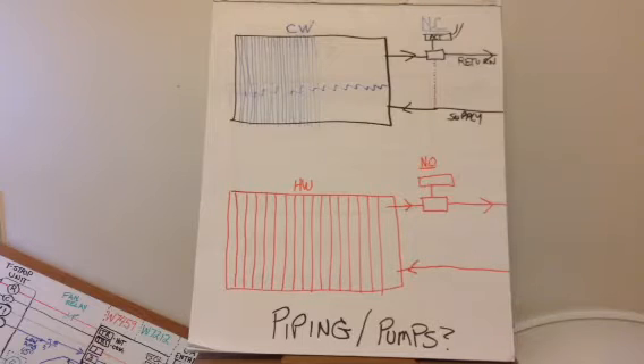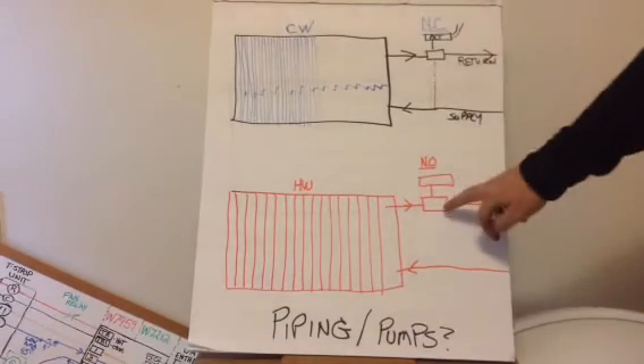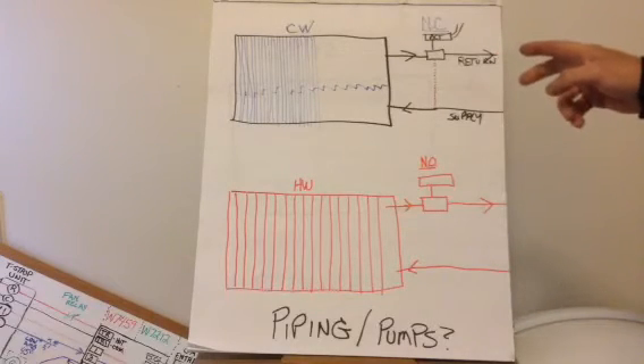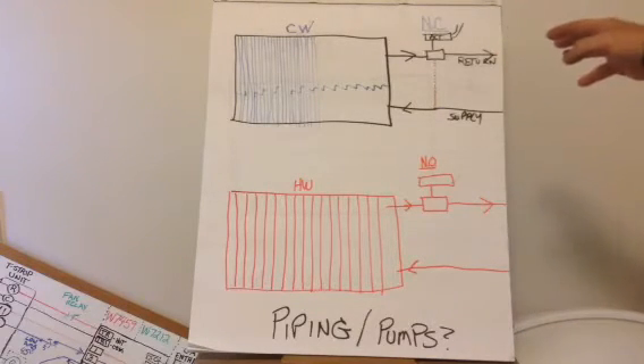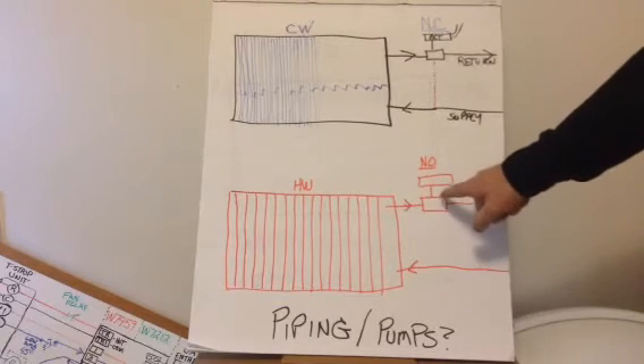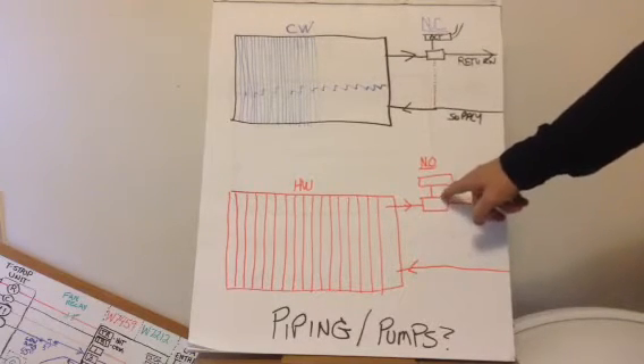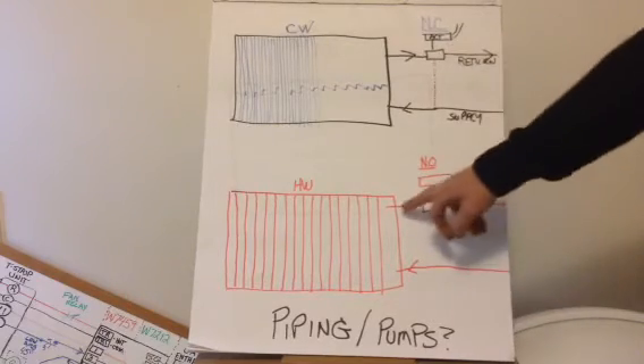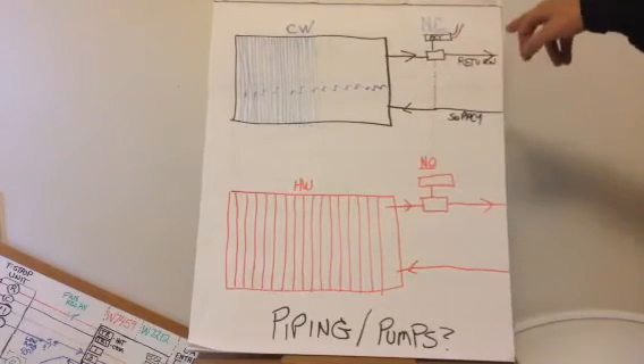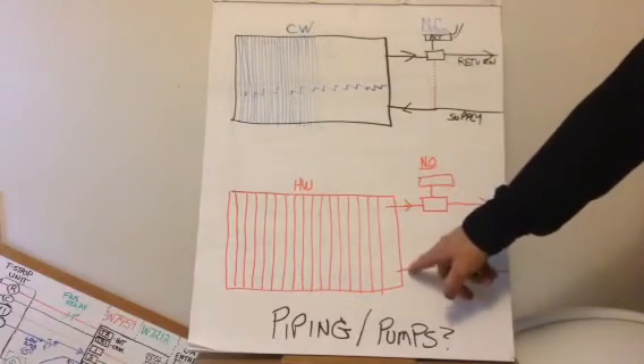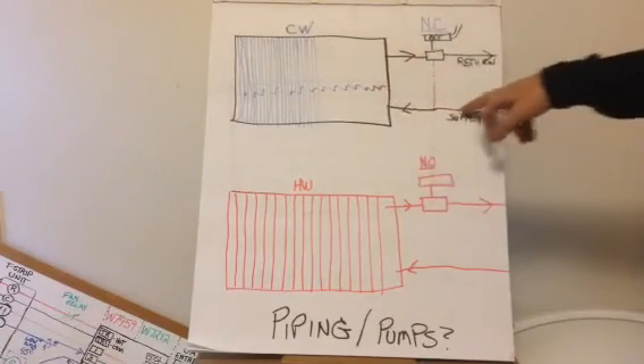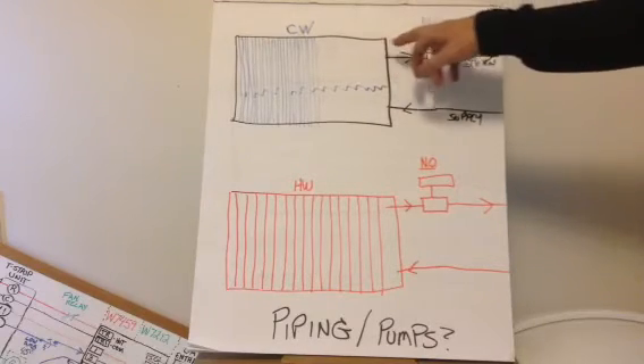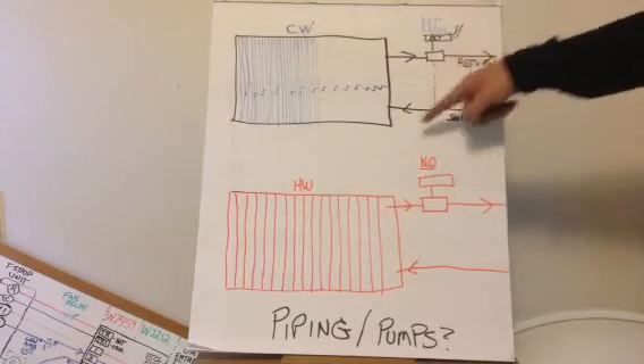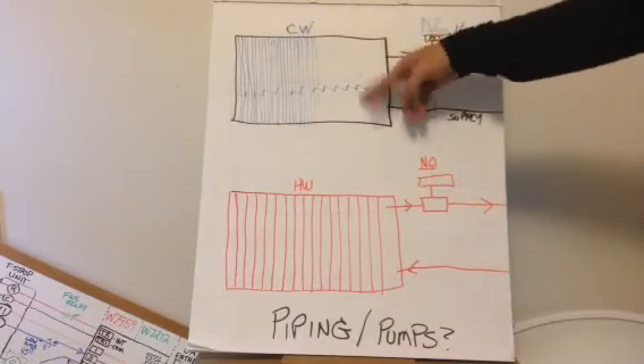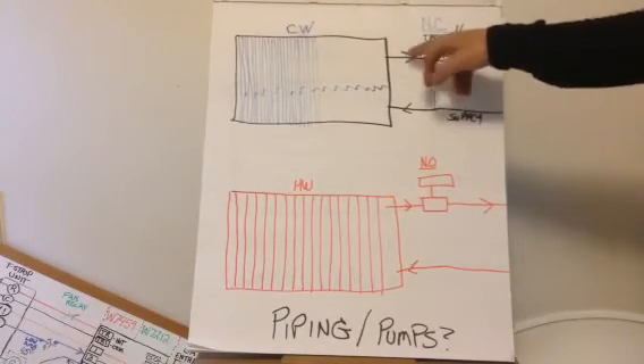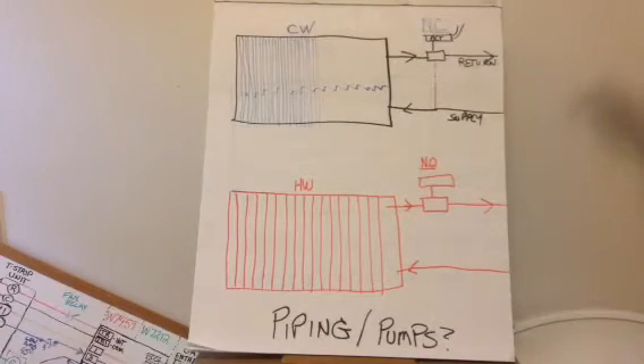Just basic thermodynamics, everyone. The other thing you'll notice here is that typically, depending on the mall again, some guys do it differently, your control valve for your hot water or chilled water is on the return pipe coming out of the unit, not on the supply pipe. For the same reason I just talked about, you want this coil full of water all the time. When the call for cooling ends, this valve shuts, this coil is 100% full of water. There's no air in it. When the call for cooling comes on, it just simply allows the water to start flowing again through the coil.